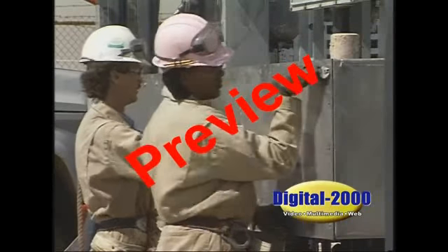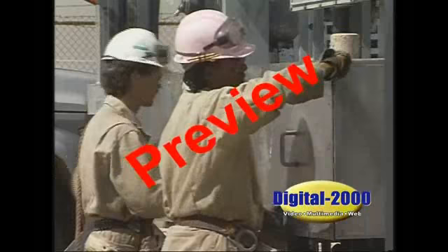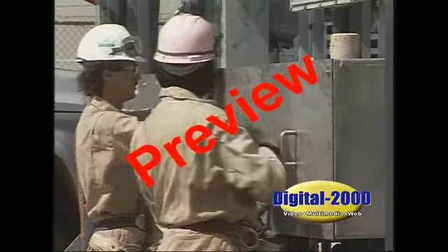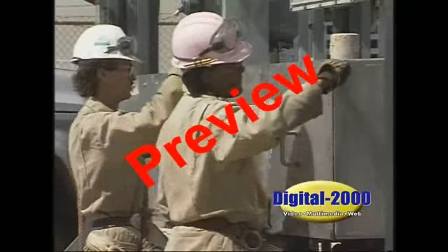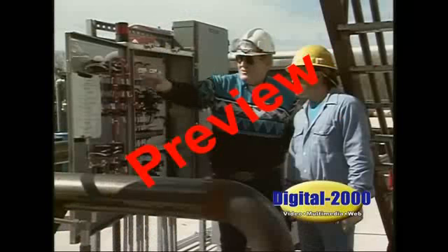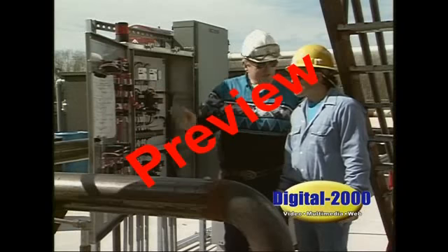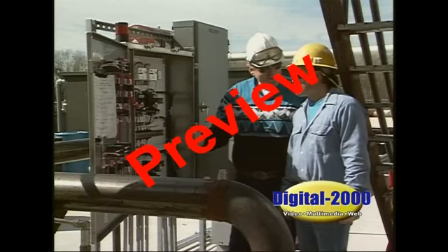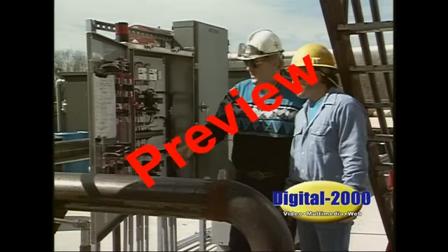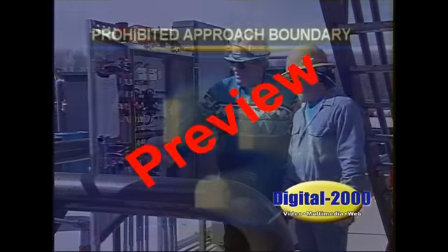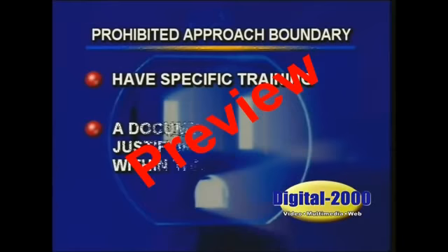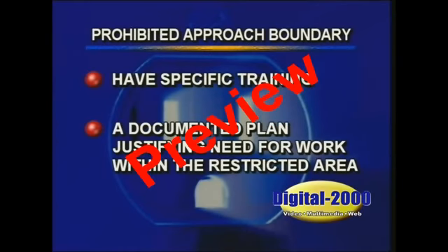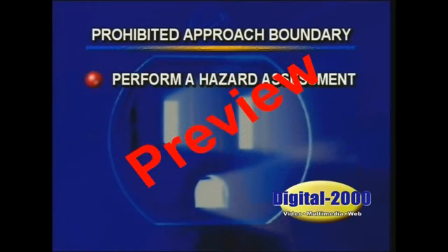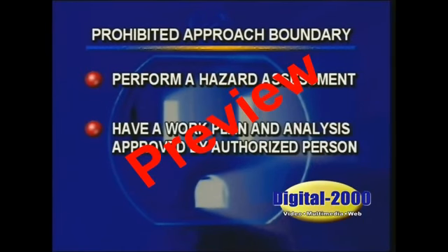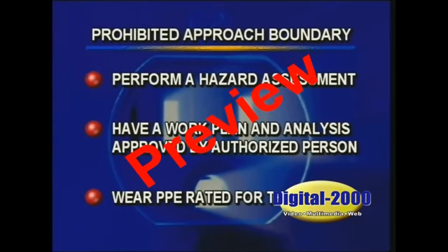Some electricians and maintenance persons will say they always work in a de-energized condition, so protection is not really needed. How does an employee know it is de-energized? To determine if it is in fact de-energized, the employee needs to test for the absence of voltage using a voltage tester. To conduct this test, he or she must enter into the prohibited or restricted area. To cross the prohibited approach boundary, the person conducting the work must have specific training, have a documented plan justifying need for work within the restricted area, perform a hazard assessment, have a work plan and analysis approved by an authorized person, and wear PPE rated for the hazard.